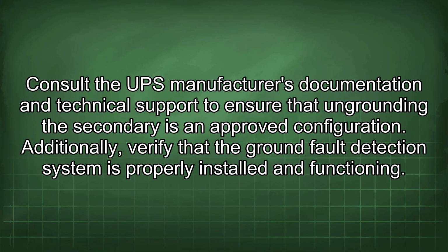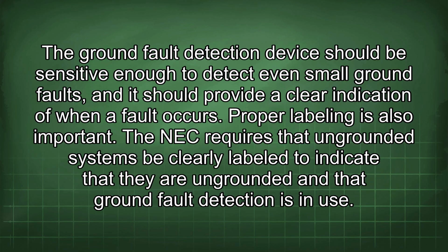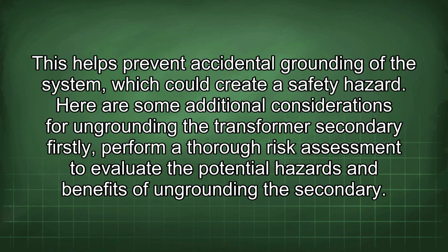Additionally, verify that the ground fault detection system is properly installed and functioning. The ground fault detection device should be sensitive enough to detect even small ground faults, and it should provide a clear indication of when a fault occurs. Proper labeling is also important. The NEC requires that ungrounded systems be clearly labeled to indicate that they are ungrounded and that ground fault detection is in use. This helps prevent accidental grounding of the system, which could create a safety hazard.